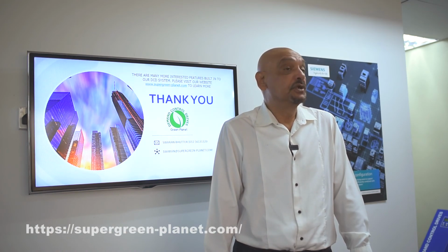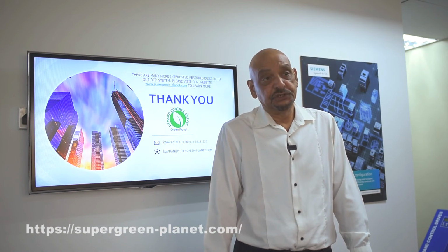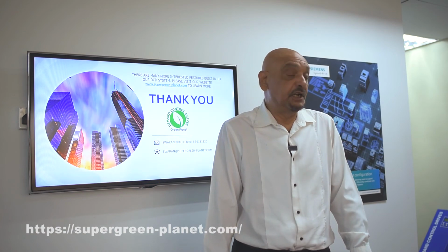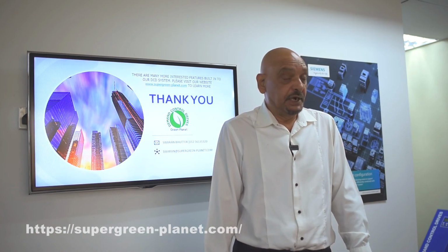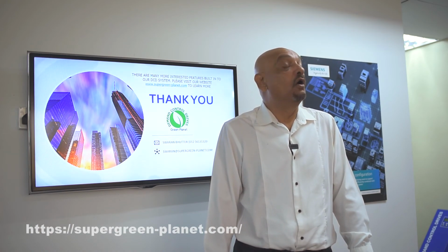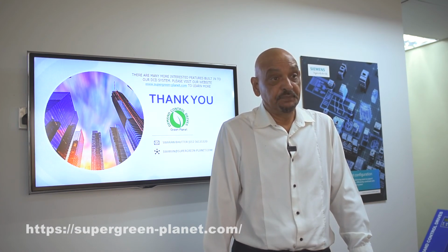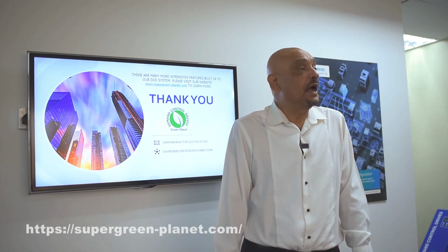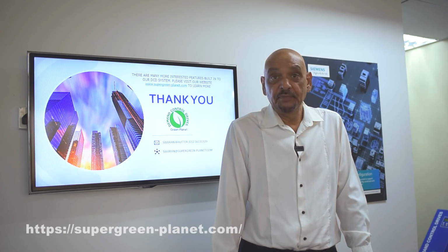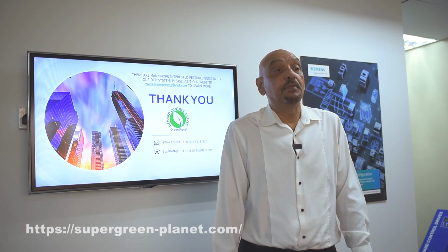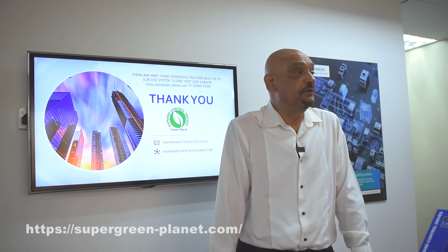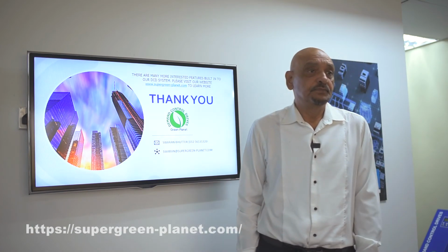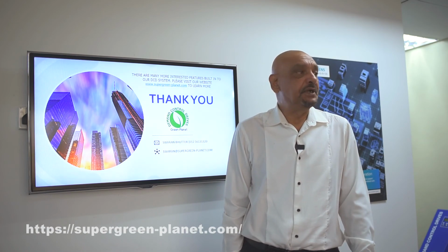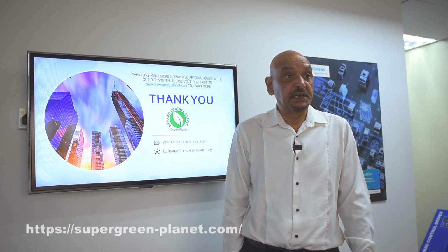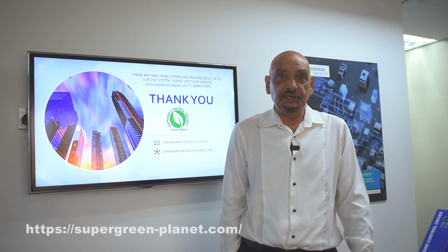Other than your reduction in your energy costs, you have got the same features which are built into your air handling unit model or your cooling tower model. You get your soft starting and all the other mechanical advantages which I have mentioned. Now, apart from that, what else are you going to get? Now, in every AHU room, you have got your existing electromechanical control panel. What we do is, we bypass that. We take in power supply from the main incoming that is going into your mechanical control panel. We channel it into the DCD.